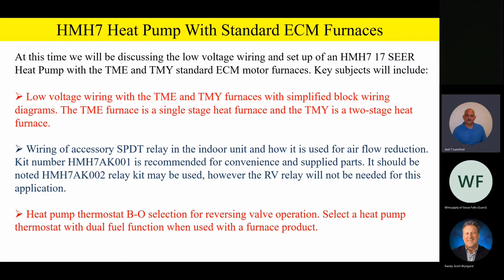Now, the burning question I've had a couple of times from contractors that get a hold of me on the telephone is, Joel, if I can't get that 001 kit or that 002 kit, can I make up my own kit with just a peanut relay and just have a switching relay? And can I use my own bi-flow filter dryer and make up my own field wiring? Well, the answer is, of course you could. It's just convenient to have all this in one place in a kit. But the truth about it is, if you were in a pinch and you didn't have a kit, you could still use just a little 24-volt coil, single pole, double throw switching relay, and put your own bi-flow filter dryer on the liquid line, because it's a heat pump, and then make up some field wiring and you'd be squared away. So it could be done in the field without this kit, but we're going to recommend these kits mainly for convenience and all the supplied parts.